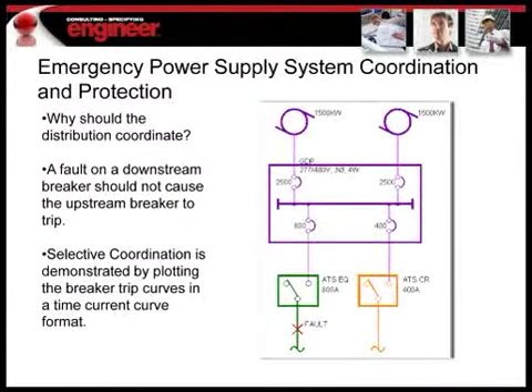Okay, so now we're looking at a simple one-line diagram, and the first question that comes to mind is, why should this system coordinate? The reason a system would have to coordinate is that if you had a fault on a downstream transfer switch or breaker somewhere down in the system, you don't want that fault to trickle through the system and trip a higher level breaker, affecting other loads. In this case, we wouldn't want it to trickle up to the generators and knock the generator offline, because knocking the generator offline would obviously affect other loads.